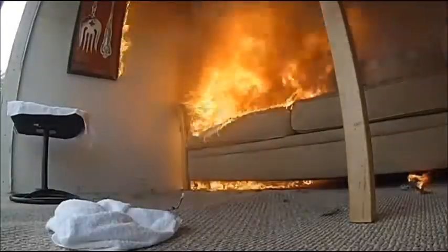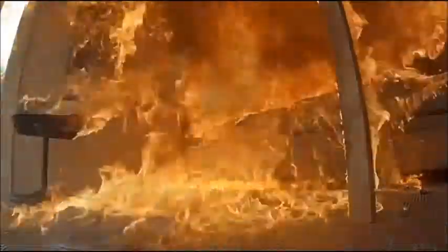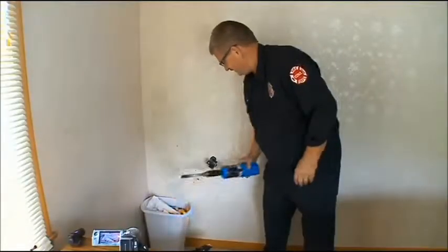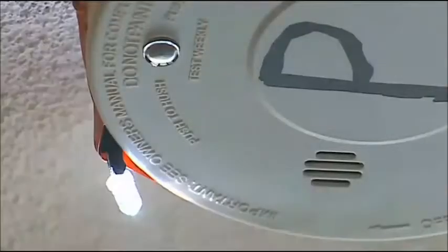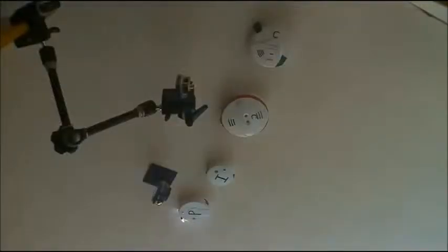So how do the smoke alarms fare in a flaming fire? We're going to show you. This is your kitchen fire, or children playing with matches. All 3 types went off within 3.5 minutes of each other. What's important to note is during our test, we could still get out safely when all of the smoke alarms sounded.